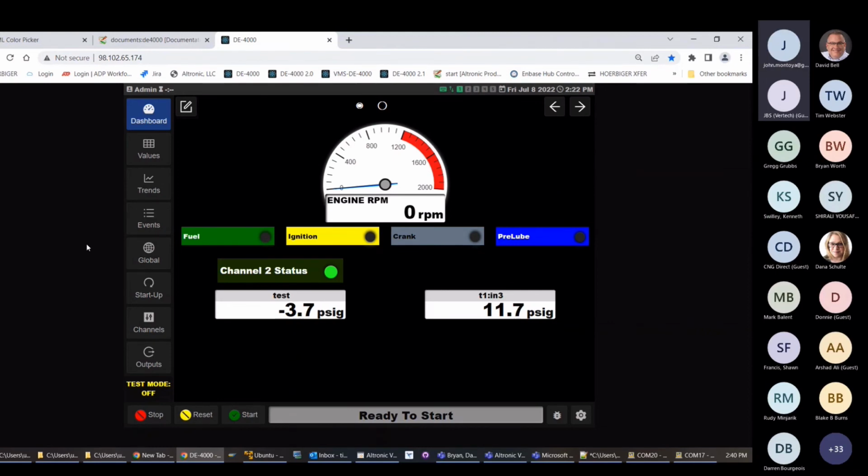We figured out that some other Modbus registers haven't been created yet, so we had to put that into the script, and we did it. But there were some others that were not possible since, in my understanding, some tags were not created in the main program. So basically, in summary, it looks like some of the information that can be achieved from the DE-3000 and DE-3000 pluses is not yet in the DE-4000. Is that something we can have in the future? Do you have that on the pending list?